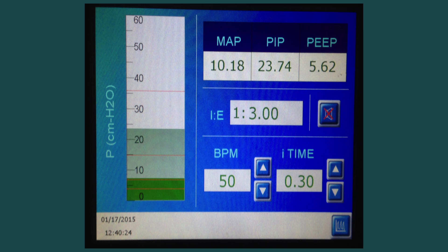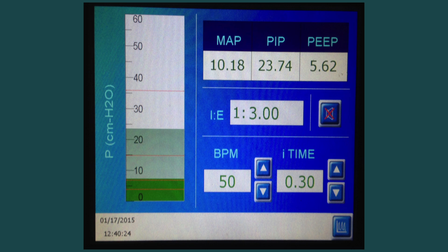There is an alarm off button which can be used to silence the alarm but only for 30 seconds for safety reasons. The bar graph on the left of the screen shows the PIP and PEEP that are generated for each breath. The upper and lower red lines are the high and low pressure alarm limits that are set for the infant.